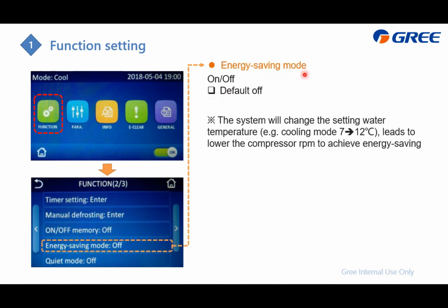Energy saving mode. When you turn on this mode, the system will change the set water temperature. For example, in cooling mode, it changes from 7 to 12 degrees. This keeps the compressor RPM from going so high, which achieves energy saving. Compared with setting it to 7, when you set it to 12 degrees, the compressor will not consume that much power.